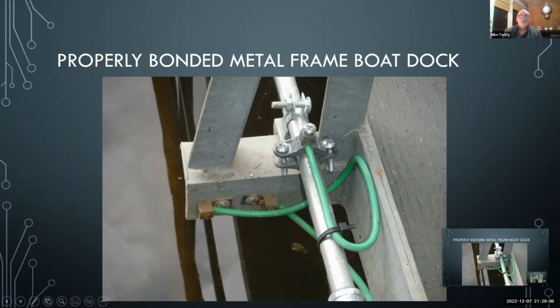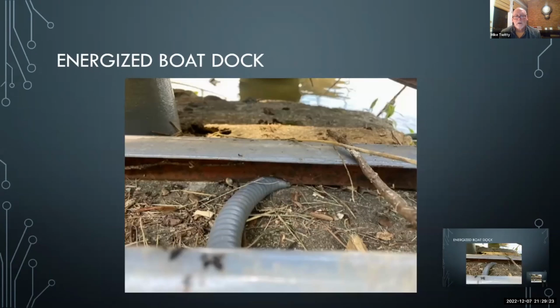If you live around lake homes and stuff, if you look at boat docks, they've got a particular set of requirements. I live on a lake up here, and I've wired probably 50 or 60 residential boat docks. So this is one that I was called out on. Actually, a neighbor across the lake from me called me and said they were swimming summer before last around their dock, and when they touched the dock to get out, they felt a tingle. What had happened, this was an old dock that was not properly bonded. This is the seal tight going out to the lights and plugs on the dock, and the water came up, had a little flood, it shifted this steel over, and it crushed this seal tight enough to cut into the hot wire and energize all this steel. It was hot. It's a wonder that somebody didn't really get hurt in that situation. Swimming around boat docks is not a good idea.